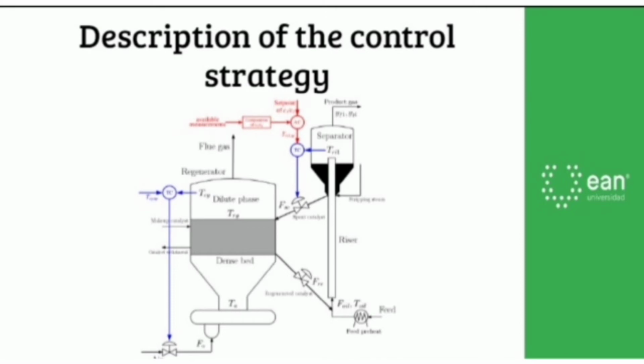3. Safe operation and stabilization remain the first priority for operating chemical plants. This can be well ensured in the upper SOC structure by simple addition of saturation blocks for the setpoints of the controlled variables so that a reasonable operating region can be maintained. The upper and lower setpoint limits can be determined based on experience gained from historical operation.